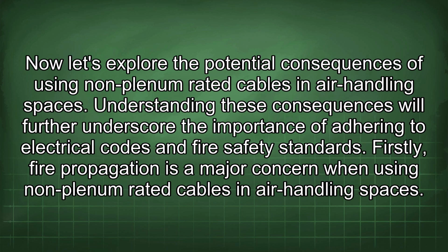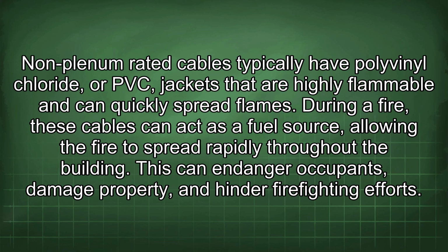Now let's explore the potential consequences of using non-plenum rated cables in air handling spaces. Understanding these consequences will further underscore the importance of adhering to electrical codes and fire safety standards. Firstly, fire propagation is a major concern when using non-plenum rated cables in air handling spaces. Non-plenum rated cables typically have polyvinyl chloride, or PVC, jackets that are highly flammable and can quickly spread flames.